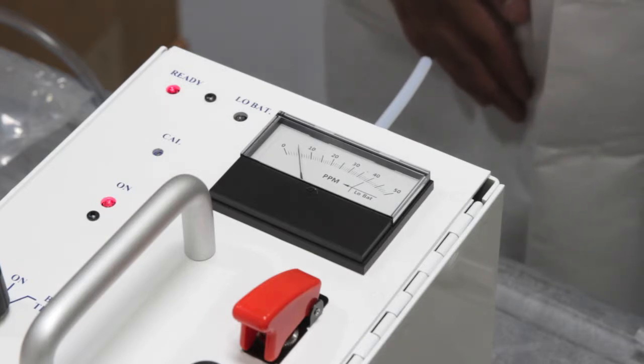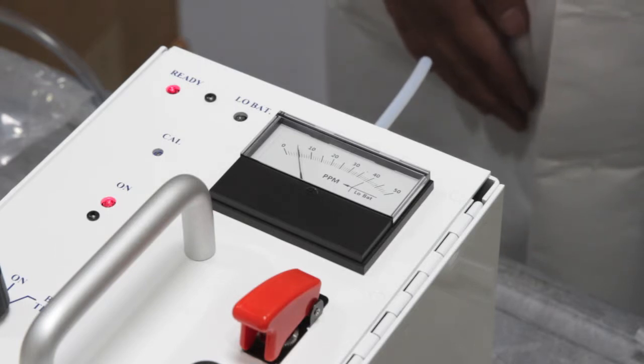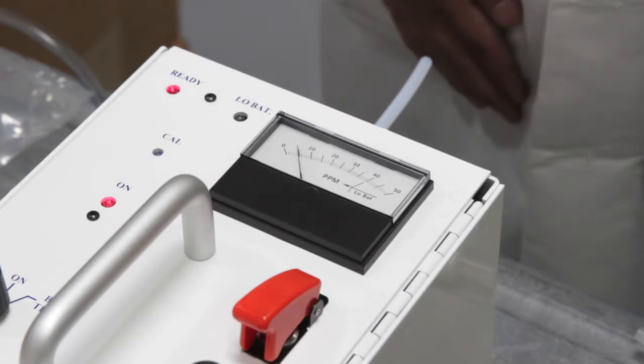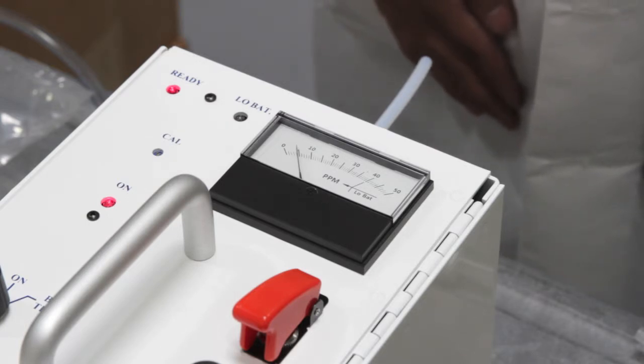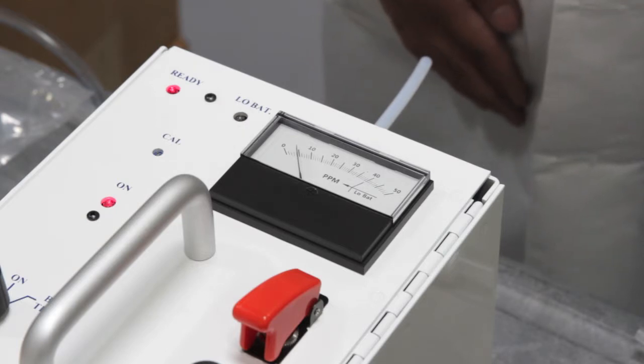Using a 5-liter bag is recommended, as it will not be necessary to refill the bag each time. In this case, do not re-zero the instrument. It is not necessary to wait for the meter to reach zero before connecting the sample gas for the second and third time. The readings should be within plus or minus 2 divisions of the average of your 3 readings.